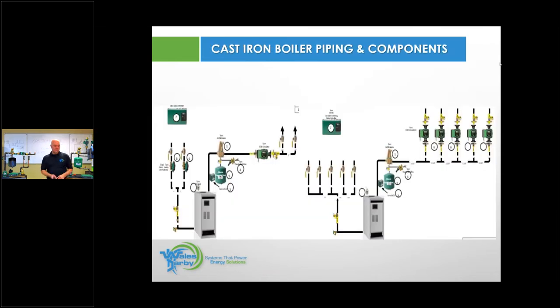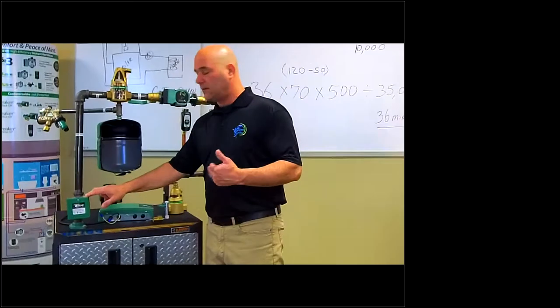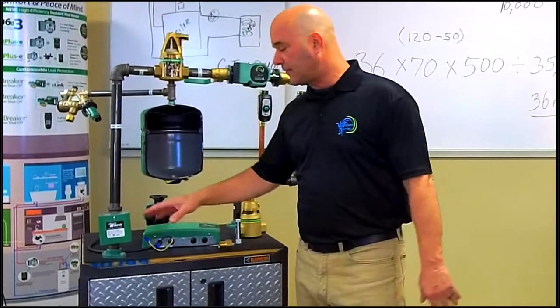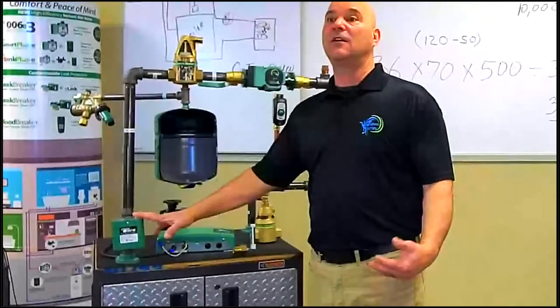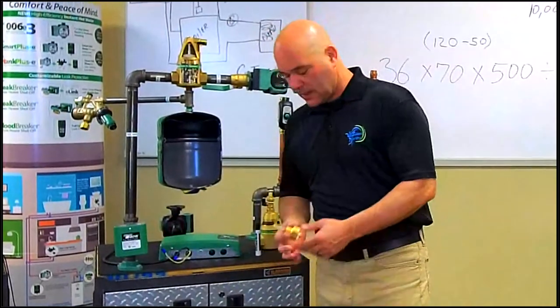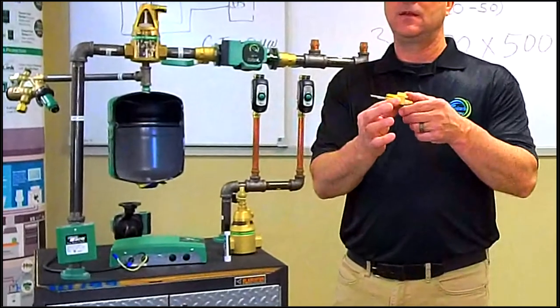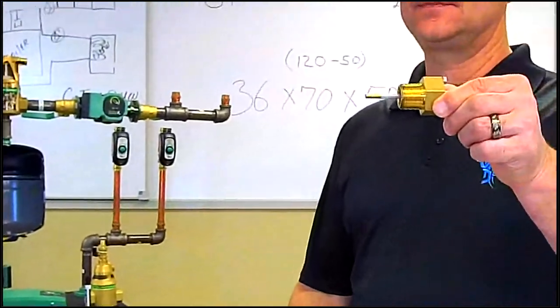Okay, so now we're going to get to talking about boilers here a little bit, because that's part of this course, right? So here we have a couple of mock boilers, and these are roll cabinets. That's pretending to be our boiler. So we mounted a couple circulator flanges on here, and we're going to go through it. So right off the top of the boiler, if your boiler has a low water cutoff, great. If it doesn't, you have an opportunity to put a low water cutoff in. Two different versions. You got a 24 volt version. You got a 120 volt version. Either or. That is going to be connected to a probe that looks like this.